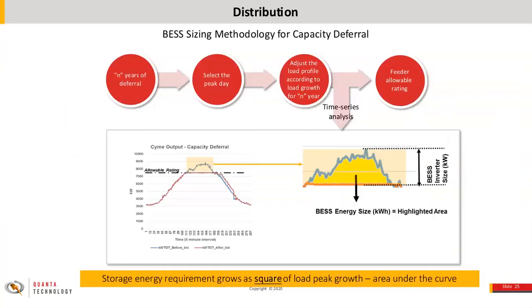Now, Hisham talked a lot about 8760, and I want to explain why it's so important. Today in the distribution world, we study the peak day and hour, or several peak days and hours, and increasingly we study a Sunday afternoon in May or September because we're looking at periods of high PV production and low load for renewables integration. When we start talking about storage, and increasingly with high renewables penetration, we have to do the same thing in distribution as is commonplace in wholesale transmission, which is to look at every hour in the year, thus the term 8760. This is a simple example of why it's important.